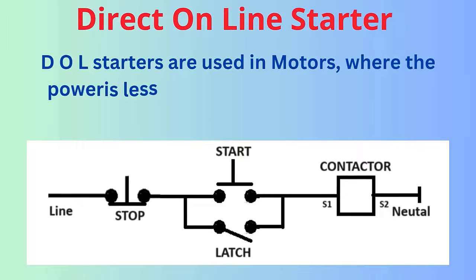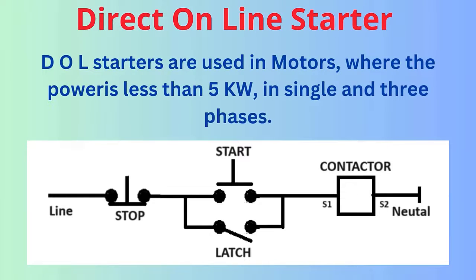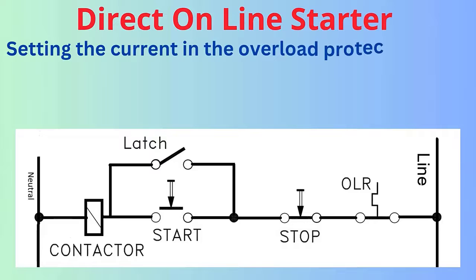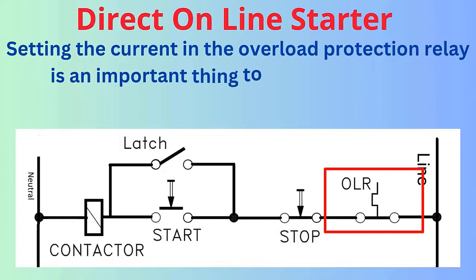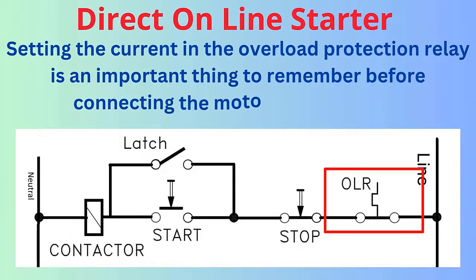DOL starters are used in motors where the power is less than 5 kW, in single and three phases. Setting the current in the overload protection relay is an important thing to remember before connecting the motor to the starters.